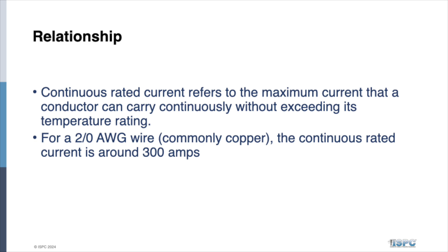So we talk about the resistance of our grounding systems, but the other thing we have to keep in mind is it's not just the resistance of that conductor, right? You could take that 2-aught ground and cut half those strands of wire going through that conductor, and I can still have a low resistance conductor. The problem is now I no longer have a conductor that can carry 300 amps. So should a fault occur on the system and my ground is not both low resistance and able to carry the current that it needs to carry to take that voltage to ground and have the protective relays respond to it, you could be setting yourself up for a very bad day, okay?